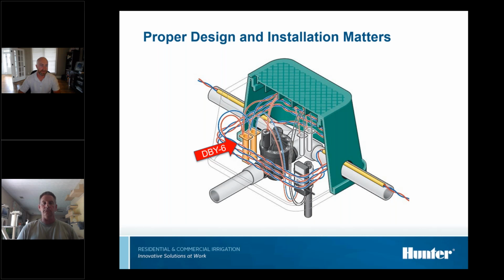Here's a great picture of what a nice, perfect installation looks like. You've got your main line coming through, your valve teeing off, then both your splices: the splice on the 2-wire path made with the DBY-6s, and the decoder over here. A good practice, not seen a lot but I like it, is using a Schedule 80 nipple driven into the ground as a stake, with a 3/4 inch piece of PVC behind it, and the decoder attached to that PVC, basically a little decoder holder, which makes troubleshooting a lot easier. So you've got the 2-wire path coming in, a nice, clean installation of a decoder in a valve box.